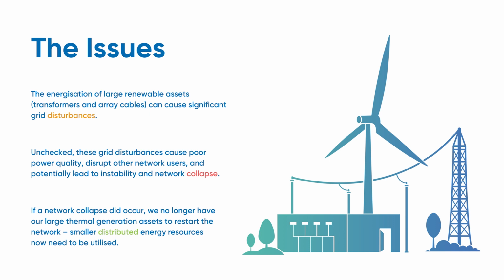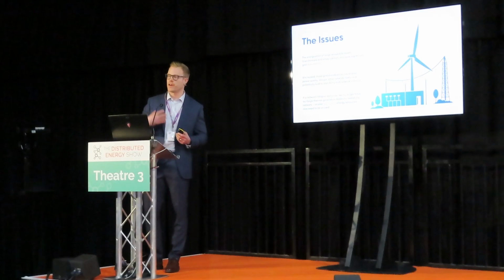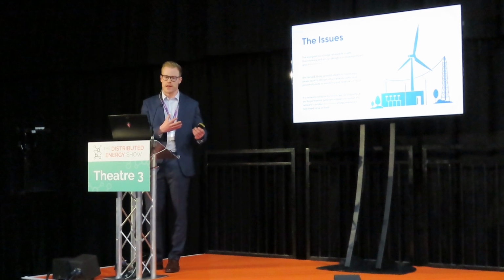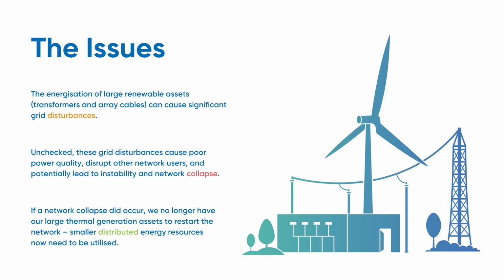So like if you were to look at a wind farm, for example, you have your grid connection, and then you have a whole array of cables. You have big transformers to take that grid connection voltage, could be 33 kV, 132 kV, and transmit it down to lower voltages of the turbines. You have to energize that site.